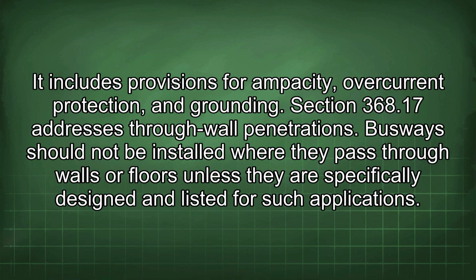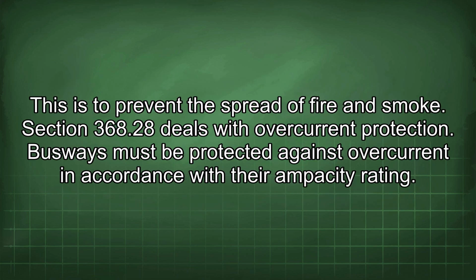Section 368.17 addresses through-wall penetrations. Busways should not be installed where they pass through walls or floors unless they are specifically designed and listed for such applications. This is to prevent the spread of fire and smoke.